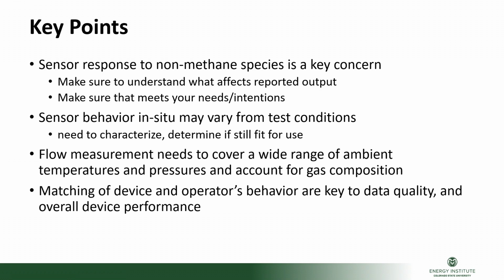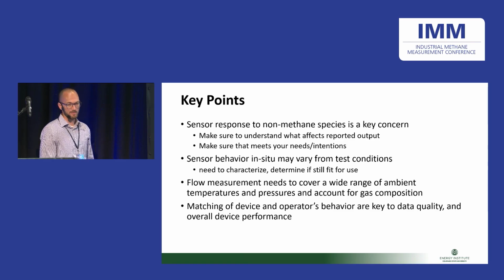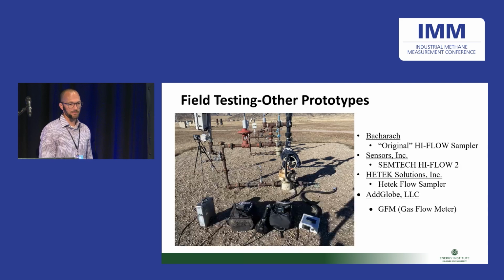the device behavior in situ is going to be very different than it was in the lab when you have a human involved. And your flow measurement needs to cover a wide range of ambient temperatures and pressures and account for gas composition. And you want to match the device and operator's behavior together. Make sure that the operator understands and is using the device in the way that you intended, or you're never going to meet your overall device performance targets that you may have achieved in the lab.